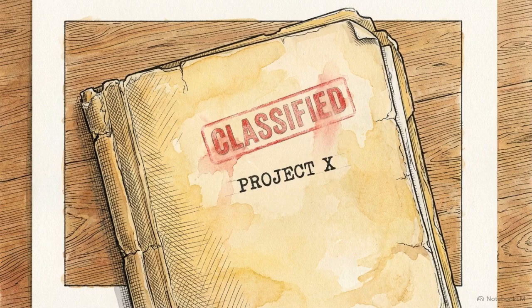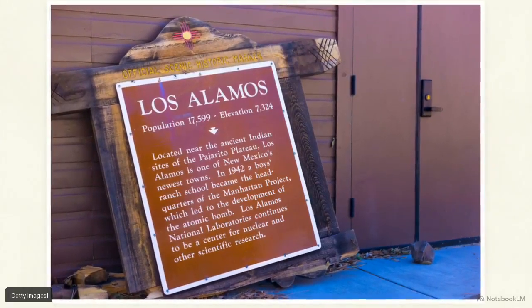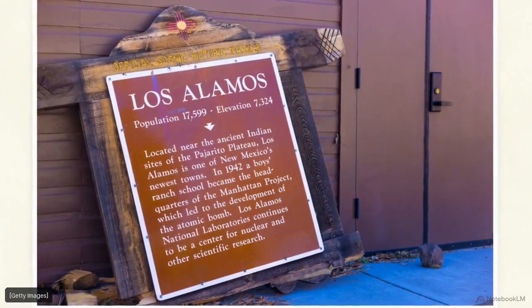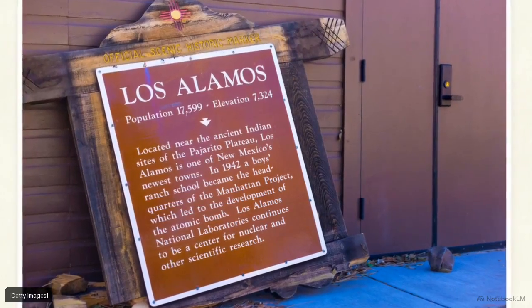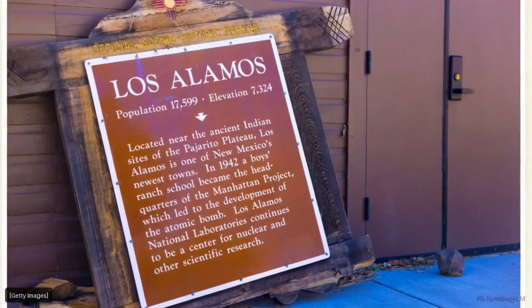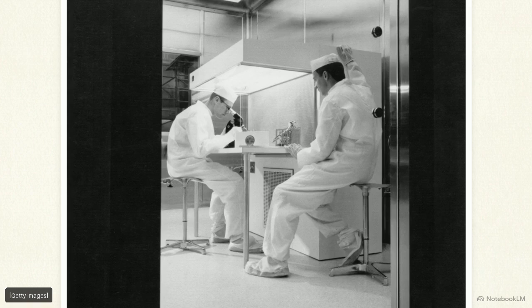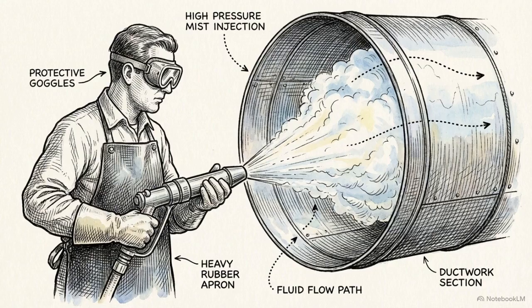The development of absolute filtration began far from the needs of modern medicine or microelectronics. As this historical marker outlines, the technology was spearheaded during the Manhattan Project, specifically to capture and contain lethal radioactive dust. This photograph shows the pioneers of those early cleanrooms. To ensure these hoods were secure, engineers needed a rigorous way to validate the air barriers. For 50 years, the industry relied on DOP. Technicians generated a thick mist of this liquid plastic, spraying it into ductwork to challenge the filters.